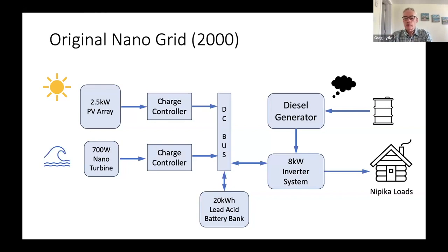The cost of solar was relatively expensive, but at the time the generator would be used to top up the battery bank when we didn't have sufficient solar resources or water resources. But you still wanted that storage because you didn't want to be running the generator all the time when somebody turns on a light. So you wanted to be essentially running off the battery bank with the diesel generator just coming on intermittently when either the inverter couldn't supply the peak loads or the other resources weren't adequate to charge the batteries.